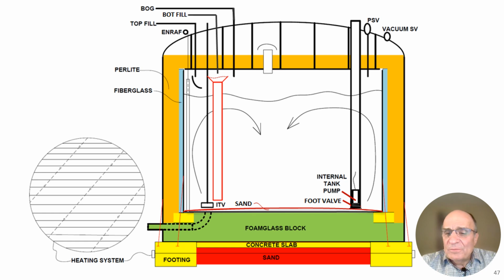Typically for internal pumps, you'd have 4 tubes, 1 of them empty, 3 of them with a pump, and that's typical. It doesn't mean that it has to be 4 with 3 pumps, but it's a typical configuration that you'd find. Let's say you want to fill the tank. Well, let's say it does not have this method of withdrawing liquid from the tank. So you want to fill the tank, you want to do a bottom fill, you can come in through your bottom penetration. You want to do a top fill, you come in and hit a splash pan and put the liquid layer on top. That's the most common configuration of older tanks.